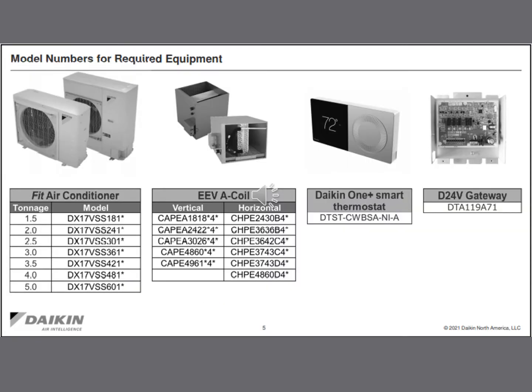So here is a list of the compatible components with the D24V Gateway. First of all, we have to use an air conditioning outdoor unit. The D24V Gateway is not compatible with the DZ17 heat pump models. AC only, no heat pump. 1.5 through 5 ton sizes of the ACs, compatible with the vertical as well as horizontal EEV coils, Daikin One+ smart thermostat, and of course the D24V Gateway. And there's your part numbers for all of those compatible components.